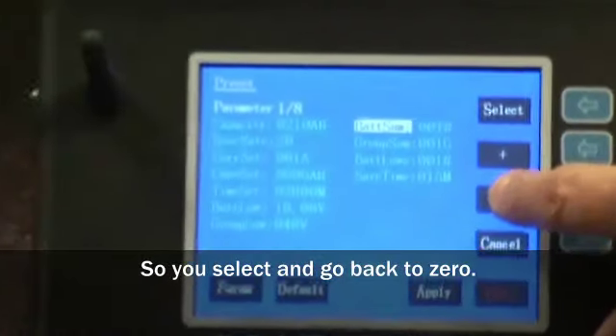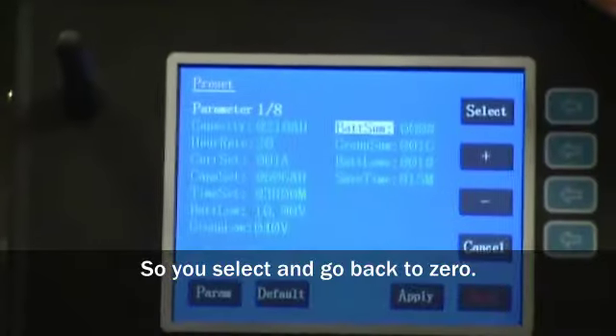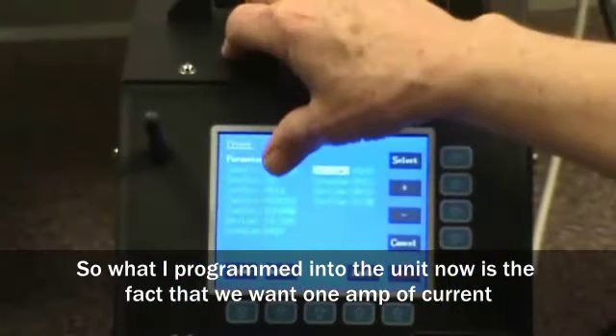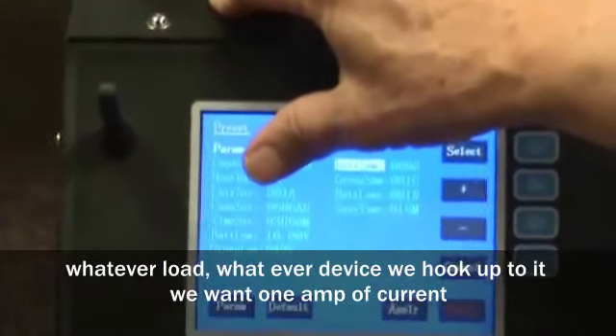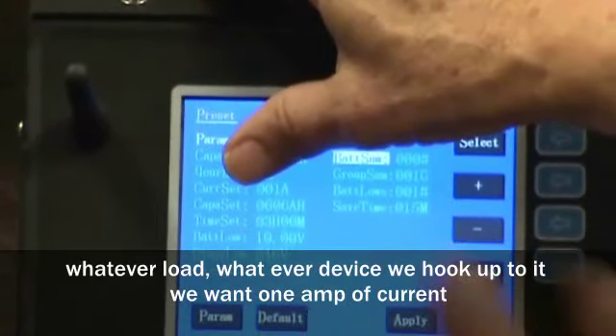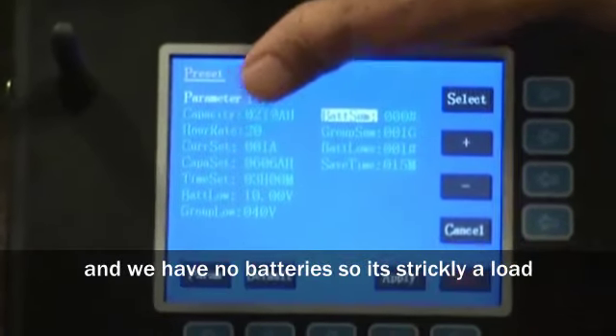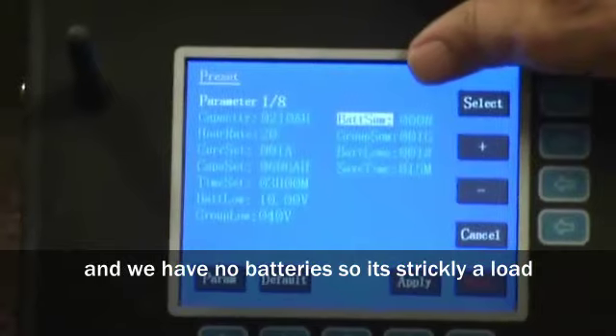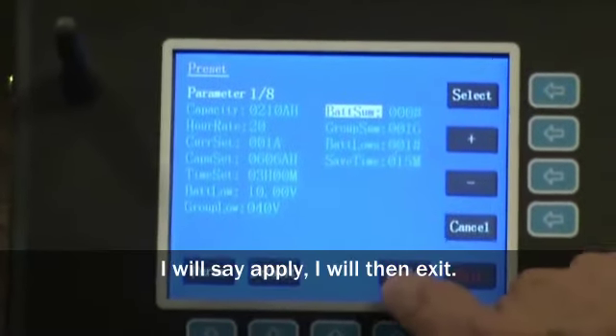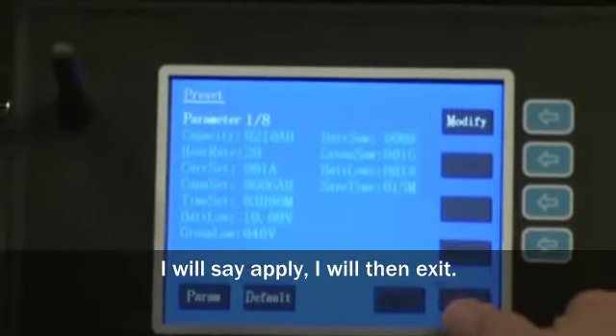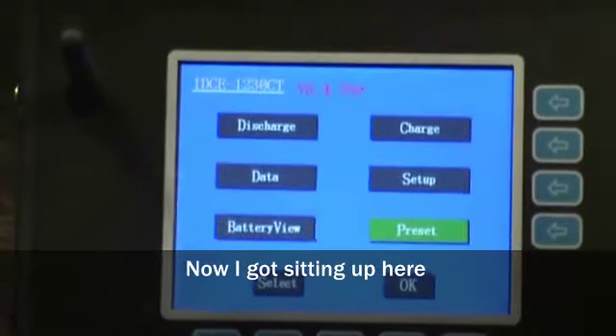So what I've programmed into the unit now is 1 amp current. Whatever load we're going to put, whatever device we hook up to it, we want 1 amp current. We have no batteries, so it's strictly a load. I would say apply. I would hit exit. I've now got the setting up here.